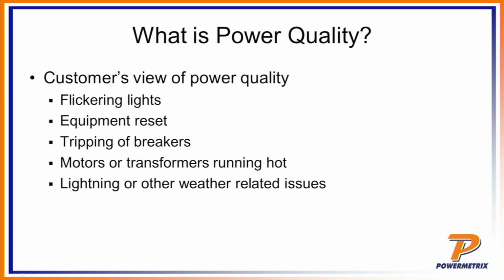If we start with the utility customer, their view of power quality is based upon what they observe. Some examples would be flickering lights. If you're having a voltage fluctuation and the lights are flickering, that happens a lot. The customer is going to call you up and say, hey, I've got something going on with that. Can you come out and take a look at my house? Equipment reset. If you've got a UPS on your PC, for example, and you're having some dropouts, some sags in your voltage, that might cause the UPS to reset and beep quite a bit, which would also result in the customer probably calling you or just trying to understand what's going on there.